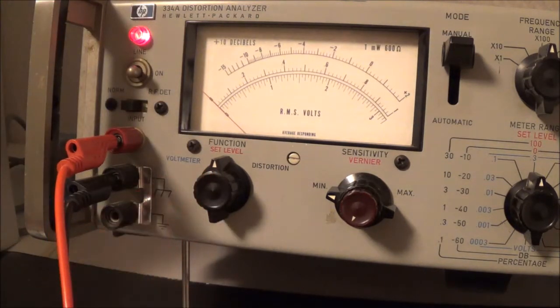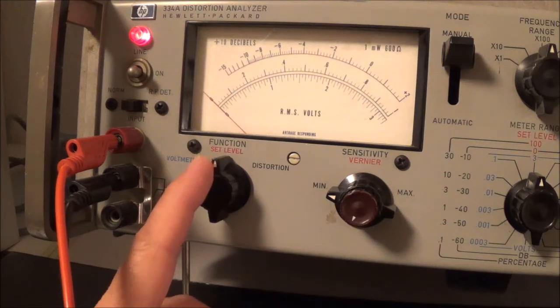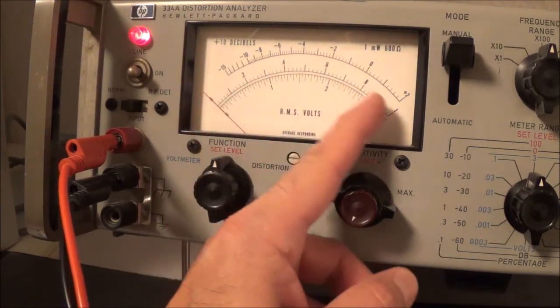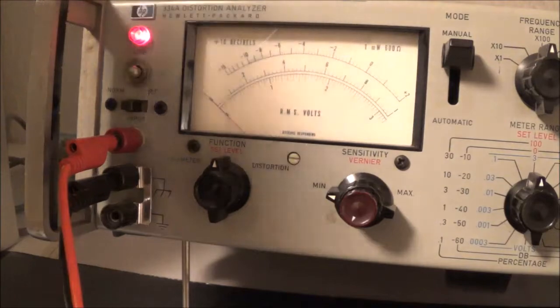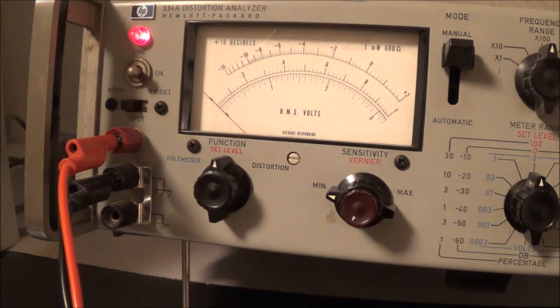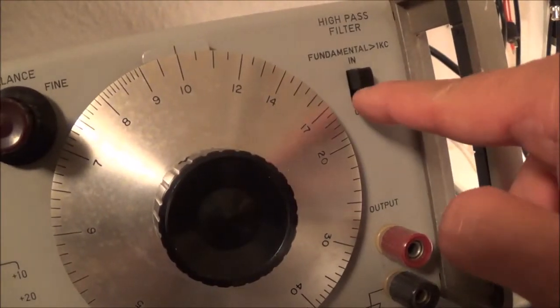And your function switch is to the set level. Set level means basically now we're just setting this thing up. What we're going to do is try to get a full scale reading here. And the mode switch has got to be set to manual. And if your fundamental frequency is one kilohertz or higher, we have to set this filter here to in.